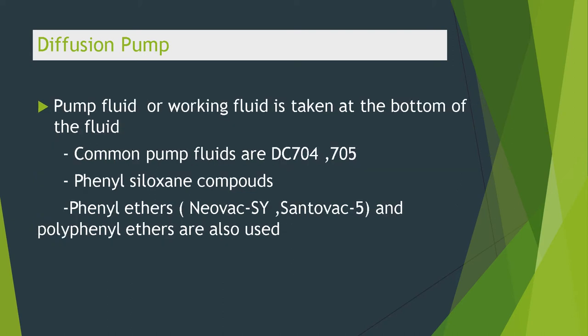The pump fluid or working fluid is taken at the bottom. The common pump fluids are DC 704 and DC 705. Phenyl siloxane compounds, phenyl ethers, Neovac SY, Santovac 5, and polyphenyl ethers are also used.